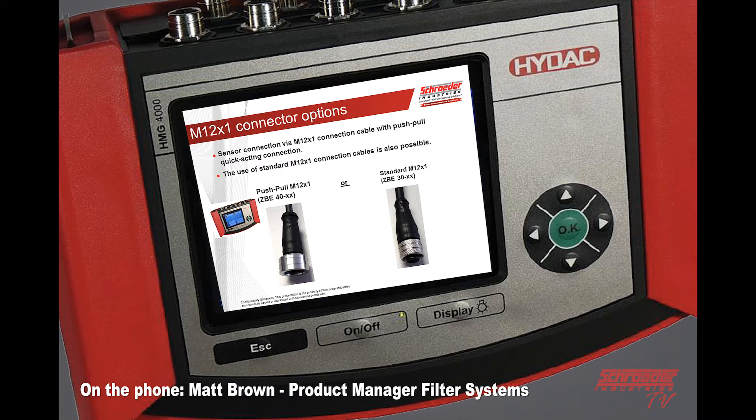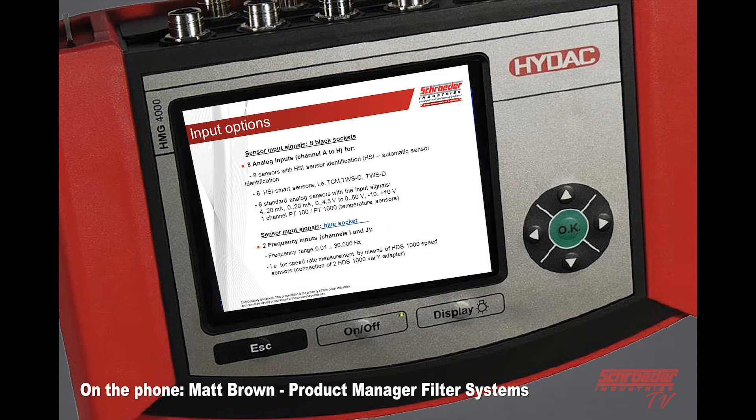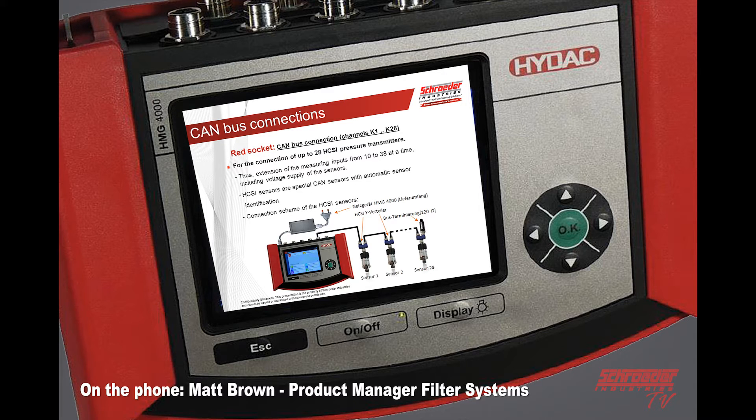You've got the push-pull M12 connector or the standard screw-type M12 5-pin connector. Channels A through H connect up to eight HSI automatic sensors — just TCMs or TWSs — or you can connect up to eight analog sensors where you would program those sensors into the system. Frequency, which is generally used for RPM, takes you from 0.01 to 30,000 hertz. On the CAN bus, it'll be one connection — you can tap into the end or tap into midstream — up to 28 HCSI pressure transmitters.